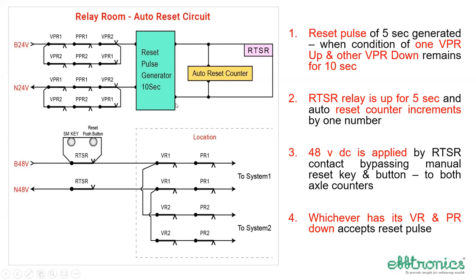This condition is applied to the reset pulse generator, and if it continues for 10 seconds, only then does it generate a pulse. That pulse picks up RTSR. The pulse width will be up to 5 seconds only, not more than that, 5 or 6 seconds. So for 5 to 6 seconds the RTSR relay picks up, and this RTSR relay applies 48 volts to the system in the location.